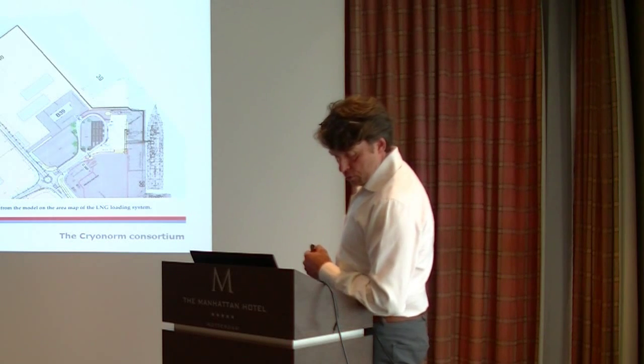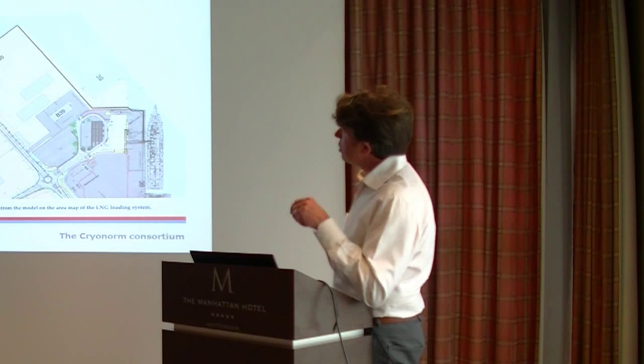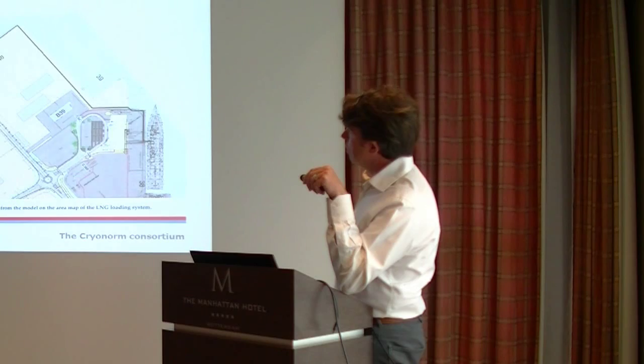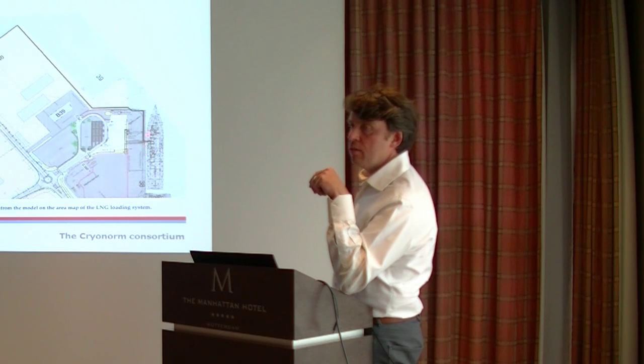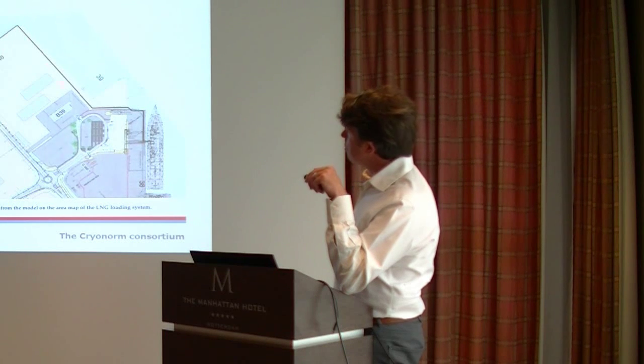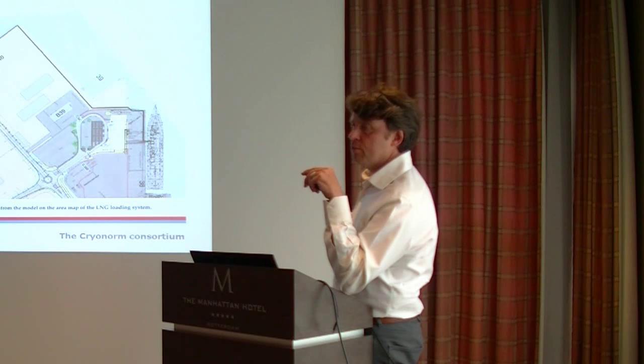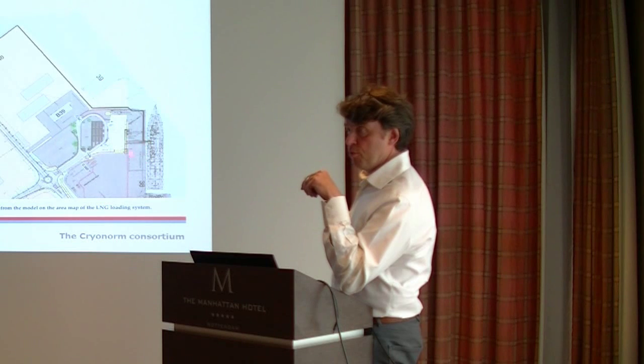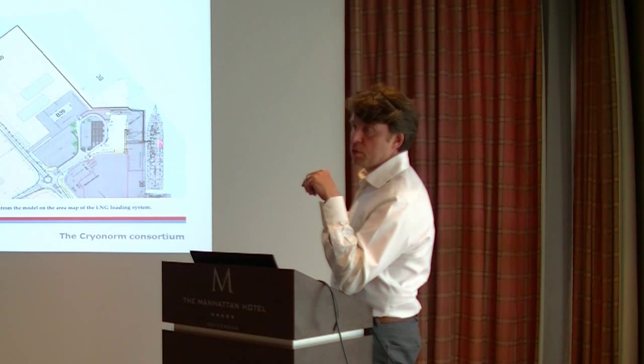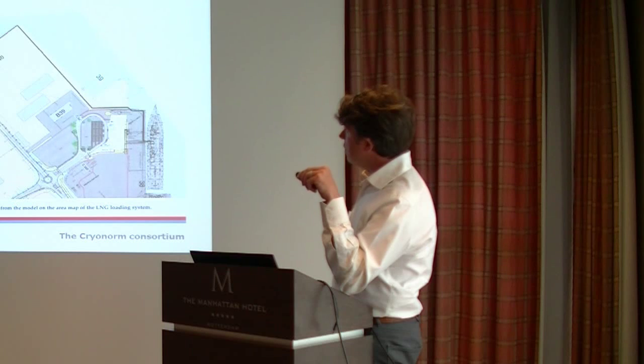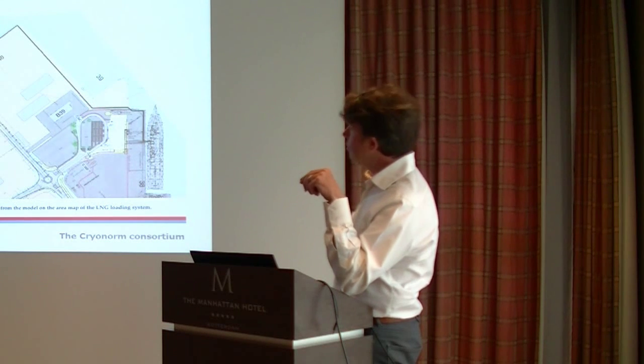One thing we had to make sure of, regarding timing, was that very early in the engineering process we decided we were going to have permanently LNG in the line. So the 630 meters of pipe being installed will be cold 24 hours a day, 7 days a week, making sure the timing for bunkering is as limited as possible. There is only one part, the loading arm, which we are going to install here, that gets cooled down at the moment the ship is actually anchored. So we will need the necessary time to cool that down to start the bunkering process. But the rest will be constantly between minus 162 and minus 152 degrees.